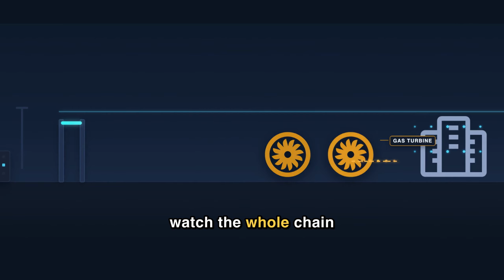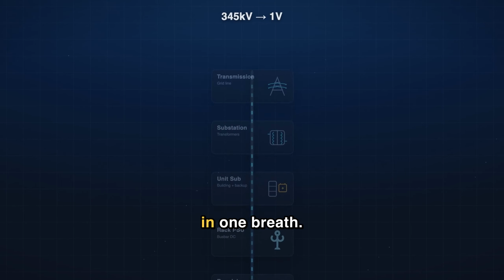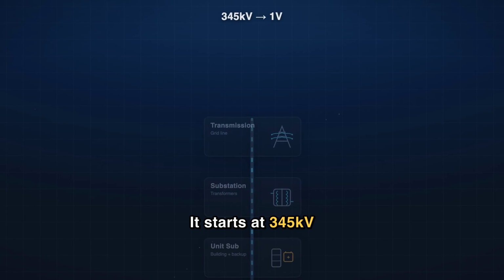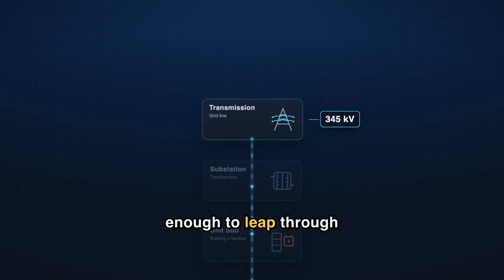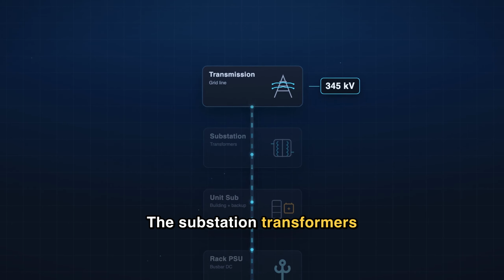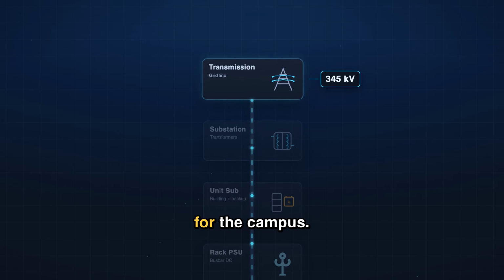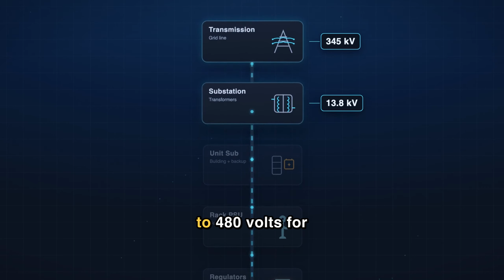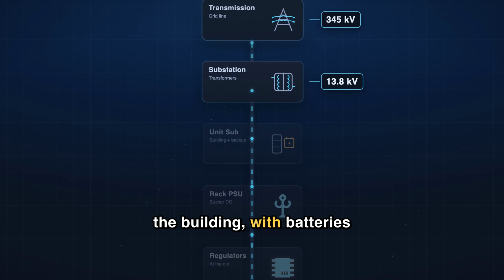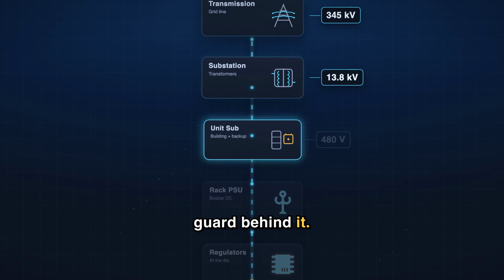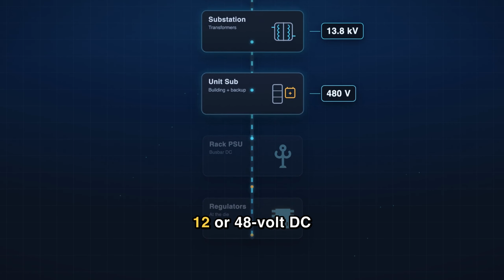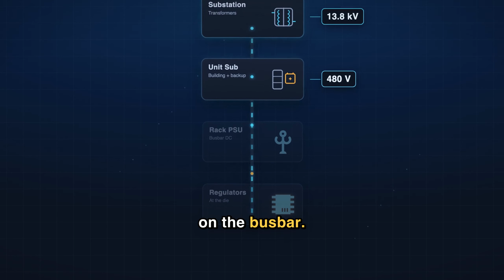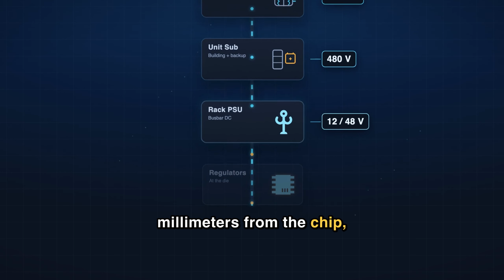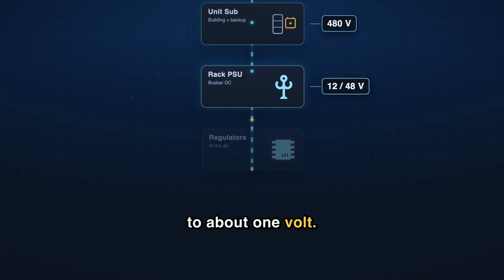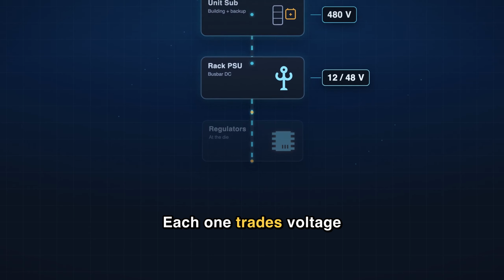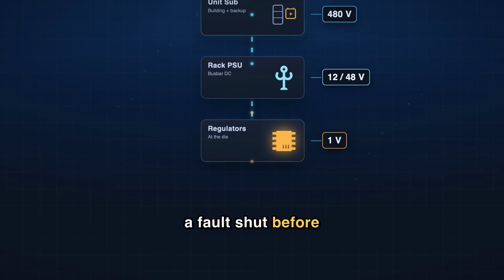So step back and watch the whole chain at once. Here's the whole descent in one breath. It starts at 345 kilovolts on the grid line, enough to leap through the air and kill. The substation transformers drop it to 13.8 kilovolts for the campus. Unit substations bring that to 480 volts for the building, with batteries and generators standing guard behind it. Power supplies in the rack turn it into 12 or 48-volt direct current on the busbar. And the little regulators, millimeters from the chip, make the final plunge to about 1 volt. 5 stages. Each one trades voltage for current or slams a fault shut before it spreads.